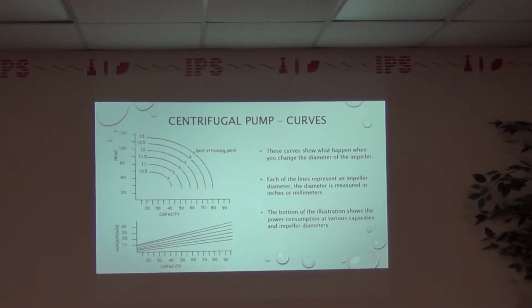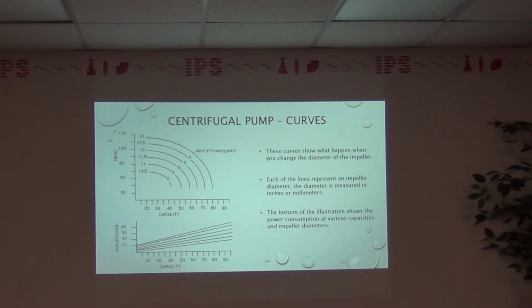Well, that's a great question. Typically, I would say you're probably in a new pump at that point, but it all depends on how they originally designed the pump. Years ago, when I came in, VFDs were the size of this wall. Now they're the size of your hand, and the price points are night and day. So people can take a pump, oversize it, slow it down by speed, benefit from the reduction in energy cost, and then have the capability to increase the speed of that pump if their demand goes up.